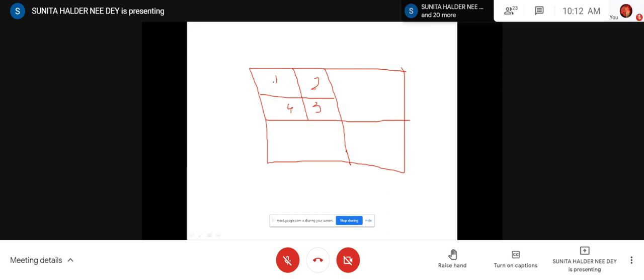So for that we need a transformer. The transformer primary, what I have told, I think 11 kV. I forgot. That is written in your notebook somewhere. Anyhow, the secondary will be 1.1. So this is the transformer, obviously three-phase. On the primary side 11 kV, on the secondary side 415 volt.